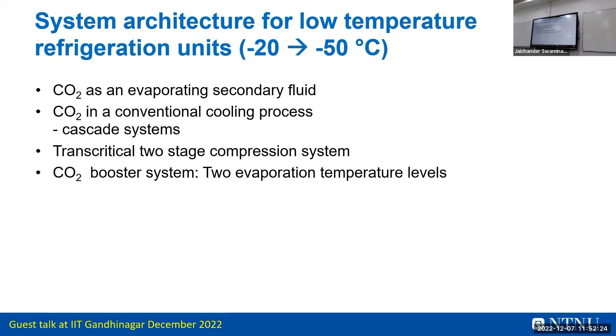The very simple one: we have a primary loop here, a chiller, ammonia or hydrocarbon system, the upper part of the cascade. Down here it's not really a cascade because we just have a loop - here we do a secondary loop with the CO2. So instead of sending the ammonia to the potatoes or to the factory where you have all this valuable stuff, or the person, you just send the CO2.